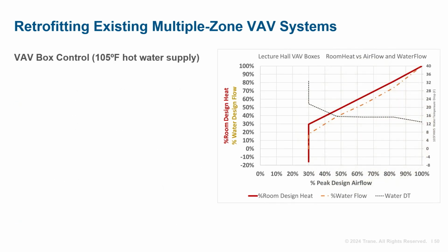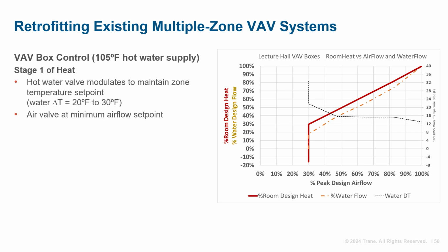Here's what zone heating with 105 degree water looks like. During stage 1 of heating, the hot water valve modulates to maintain zone temperature at set point, with the air valve at minimum airflow. During stage 1, the water delta T is 20 to 30 degrees. For most buildings, the majority of heating hours are in this stage.